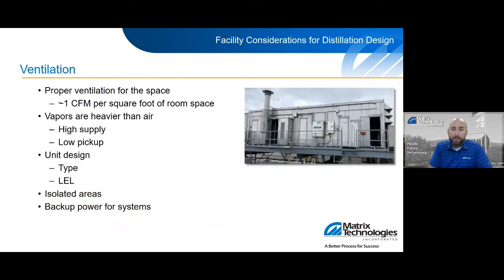And finally, it's almost over. The rule of thumb for ventilation for the space is really 1 cubic foot per minute per square foot of room space. So if you've got a 10,000 square foot room, you want a unit that's capable of 10,000 CFM. Because the alcohol vapors are heavier than air, it's critical that you have a high supply and a low pickup to make sure that you exhaust those vapors in the space.